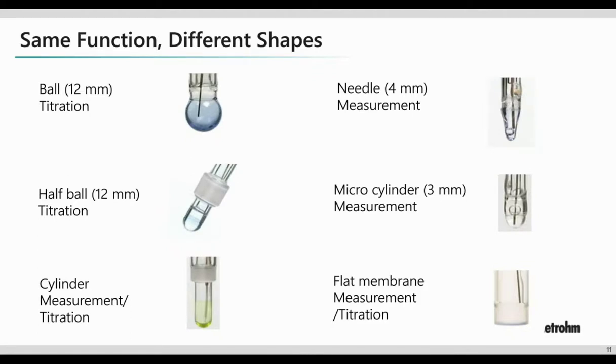The easiest way you can tell that there's a difference or something going on is just to look at the color of the glass. So you see the images on the left-hand side of your screen. That gives you some examples. So blue, some is clear, some is yellow. You also may notice that sometimes they have different shapes. So this is a simple way to make sure that we can get the entire electrode design into the sample. So on the right, you'll see some different designs. So the top one is kind of a needle or a taper design. And this is really helpful if you've got semi-solid or thicker, kind of more viscous samples. So think yogurt or a soft cheese or something.